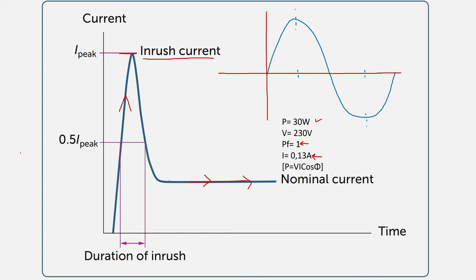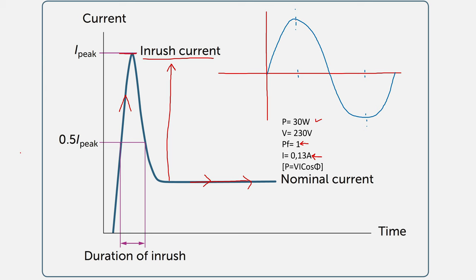Unfortunately, when the light turns on it has quite a high inrush current, and that inrush current depends on a few factors. One factor is where the voltage wave happens to be when you turn on the power. For example, if you turned on the power and the voltage happened to be at 90 degrees phase angle, we would see a sudden increase in voltage as soon as you close that switch.